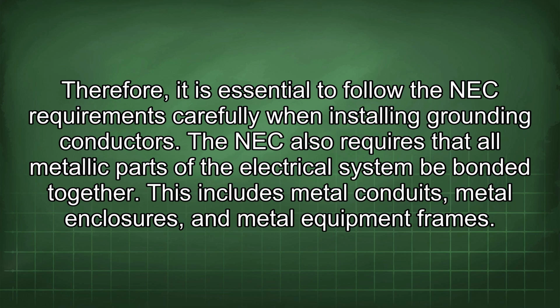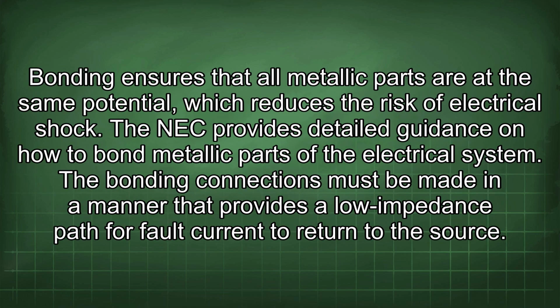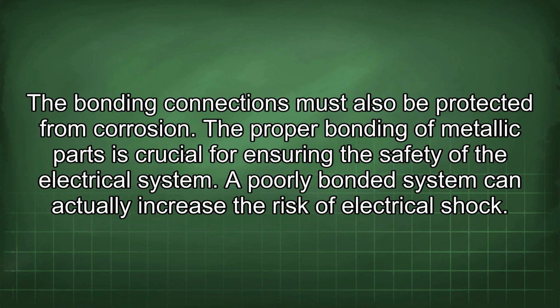The NEC also requires that all metallic parts of the electrical system be bonded together. This includes metal conduits, metal enclosures, and metal equipment frames. Bonding ensures that all metallic parts are at the same potential, which reduces the risk of electrical shock. The NEC provides detailed guidance on how to bond metallic parts of the electrical system. The bonding connections must be made in a manner that provides a low impedance path for fault current to return to the source. The bonding connections must also be protected from corrosion.